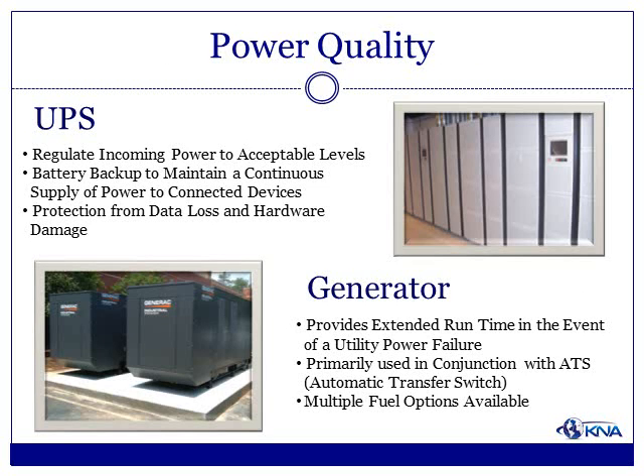Whether the customer requires smaller UPS units or industrial-sized units with megawatt capacity, KNA is well versed in the latest UPS technology. We understand what the strengths are of various manufacturers and use that information to determine which UPS best fits an application. A UPS has the ability to regulate incoming dirty power, which means utility power may have sudden fluctuations. Another benefit is battery backup to maintain a continuous supply of power to connected devices. The amount of battery runtime can be from minutes to hours and typically is determined by the customer's requirements. Utilizing a UPS provides greater protection from data loss and hardware damage.